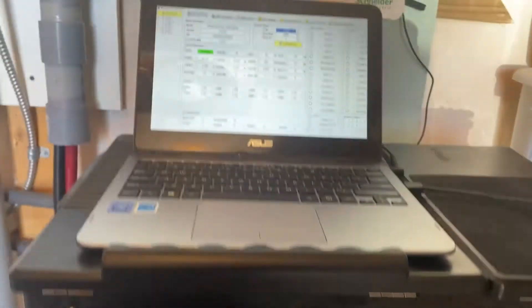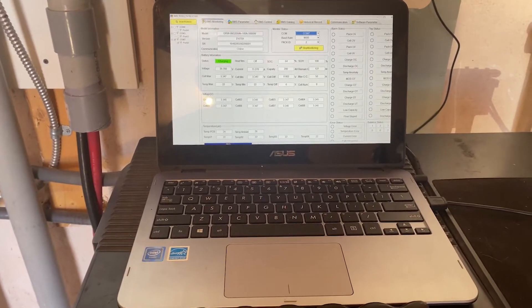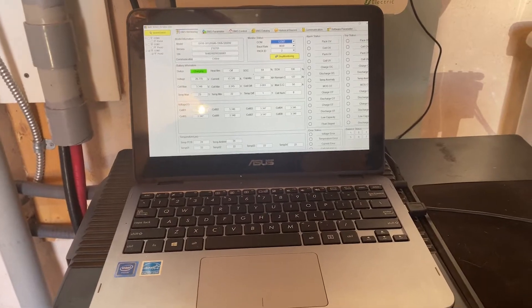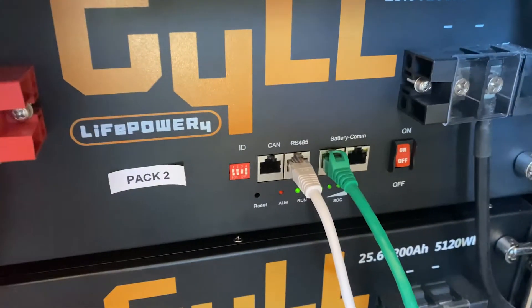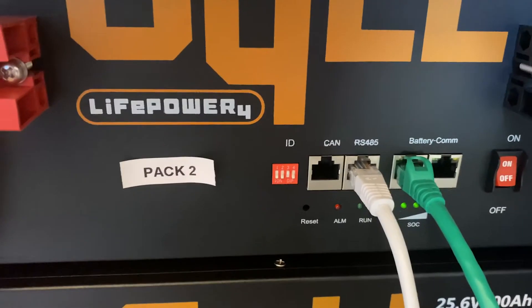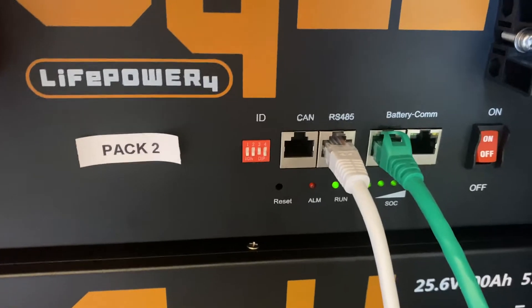When I initially installed this we were having a little trouble with the BMS software — the battery management system software. I got on the phone with the good people at Signature Solar and we figured out that this was a brand new model of battery that actually has four different RJ45 Ethernet connections. We determined that the newest models of batteries now have a CAN connector, which is a battery monitoring protocol used by some manufacturers.